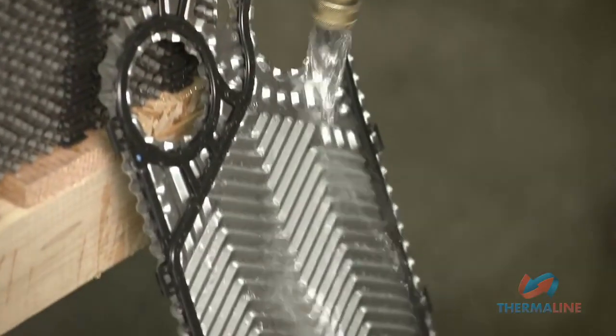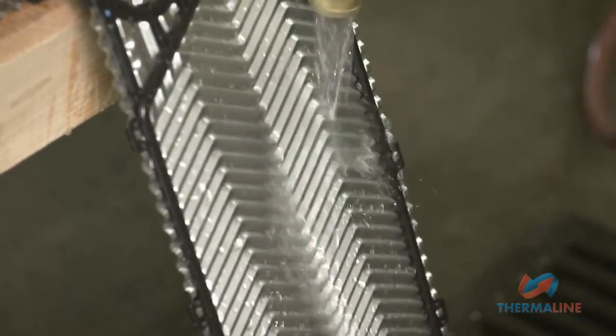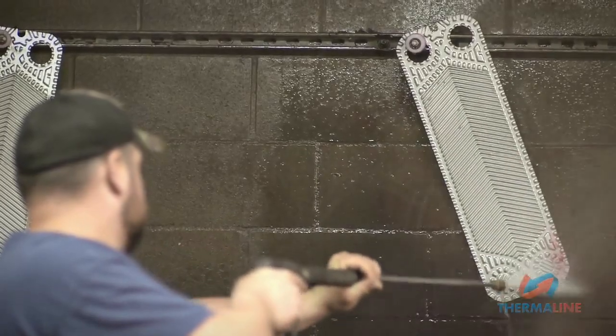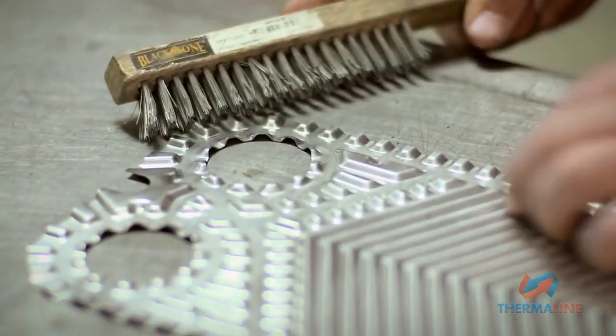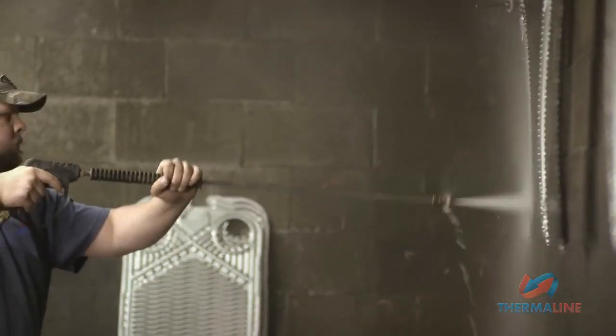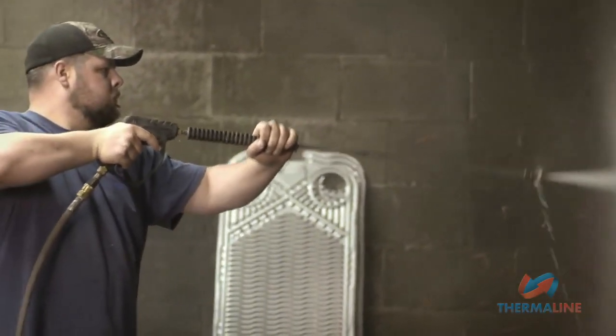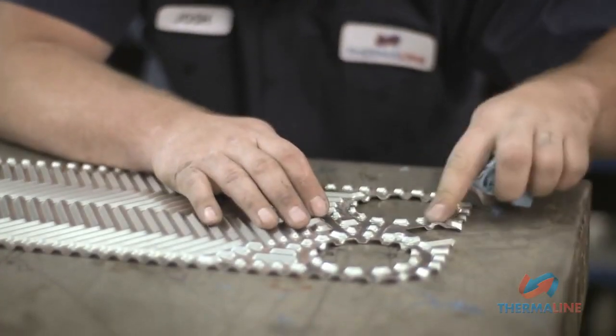The method of cleaning the plates depends on the foulants. Loose debris can be washed with soap, water, and a soft bristled brush, or a high-pressure washer. Do not use abrasives or hard bristled brushes. Wash the plates until all debris is removed, paying close attention to the gasket groove.